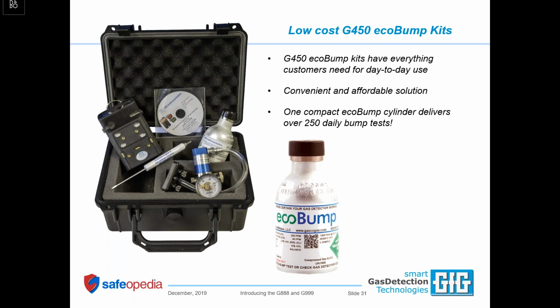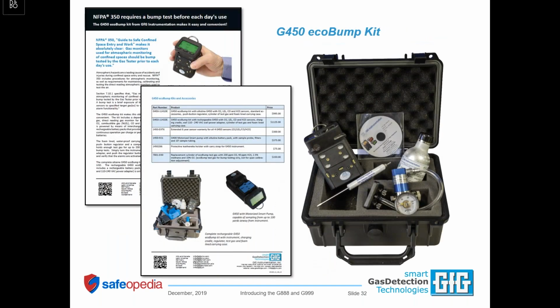So one of the things we've done this last year for all of our multi-sensor instruments is package them in the form of what we call EcoBump kits. In the case of a G450 EcoBump kit, you have everything you need in a very compact, economical package, which includes a cylinder of test gas good for 250 or more daily bump tests. The price for the compliance end of our product spectrum, the alkaline G450 EcoBump test kit, complete with the instrument, is less than $1,000. If you go with the rechargeable version, list price is $1,125. From a compliance instrument standpoint, that's an extraordinary value.